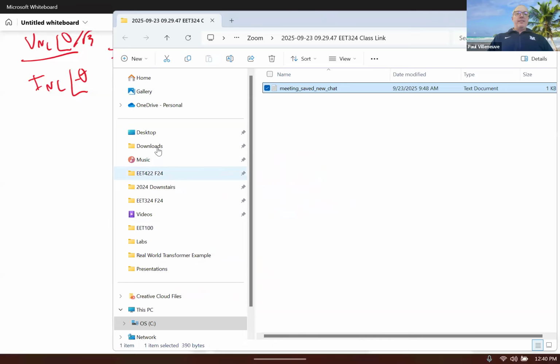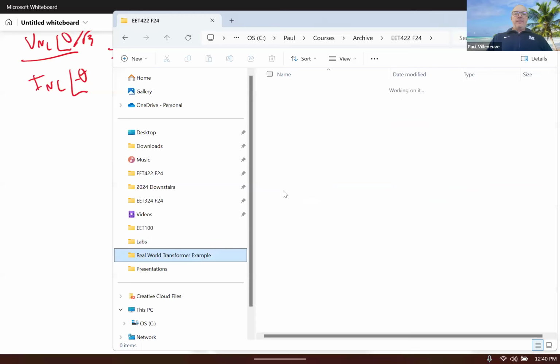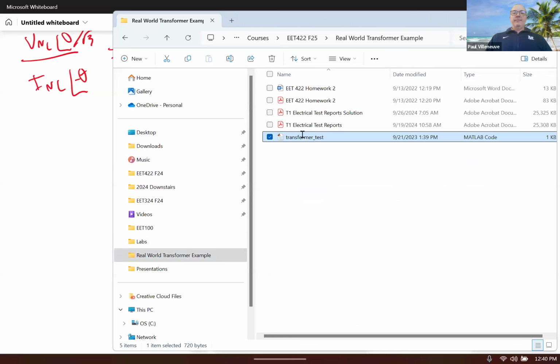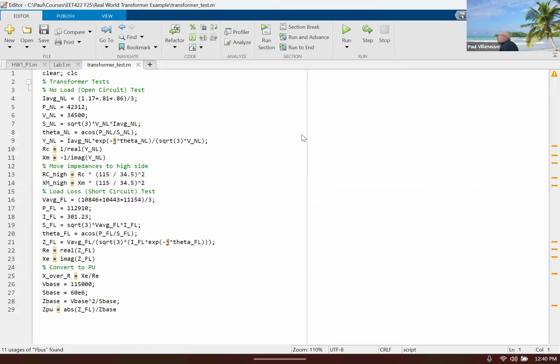Okay. Here is the MATLAB file that solves for it. So you can see I did the no load. I took the average for the currents. I grabbed my P no load, my V no load, then my S no load, square root of 3 times those. Then I calculated theta, I called it no load. Then I solved for Y. Notice, right? I took my I and divided it by the square root of 3, which means I just moved it into the denominator. It's the same thing. Multiplied by my V no load, which has no angle. And then I associated my RC and XM. Then I moved those impedances to the high side of the transformer using the turns ratio squared. That's all I did. So I actually showed those on one side of the transformer, on the high side.